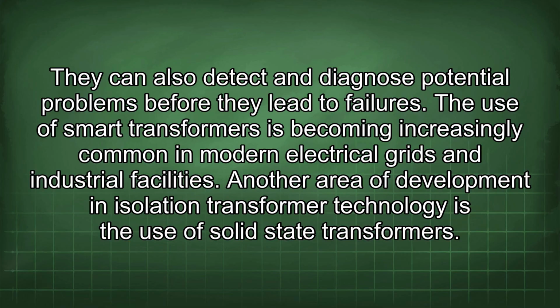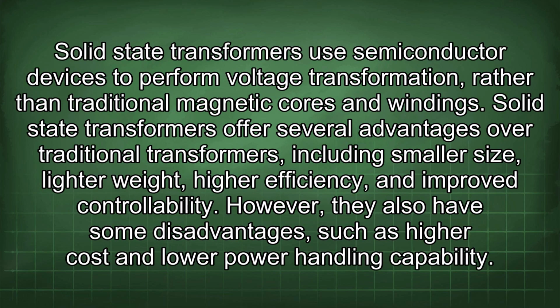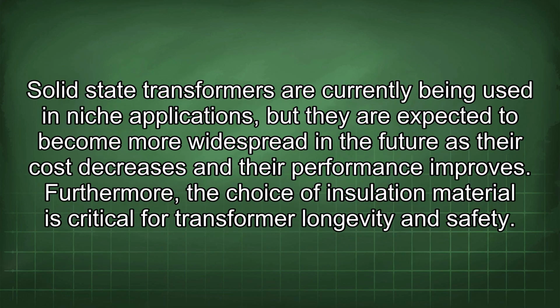Another area of development in isolation transformer technology is the use of solid-state transformers. Solid-state transformers use semiconductor devices to perform voltage transformation, rather than traditional magnetic cores and windings. Solid-state transformers offer several advantages over traditional transformers, including smaller size, lighter weight, higher efficiency, and improved controllability. However, they also have some disadvantages, such as higher cost and lower power handling capability. Solid-state transformers are currently being used in niche applications, but they are expected to become more widespread in the future as their cost decreases and their performance improves.